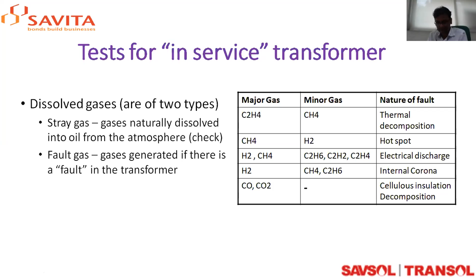So majorly, when you do the DGA, you have to keep an eye on methane, hydrogen and acetylene generation. In a transformer, acetylene and ethylene are the most critical; when there is an increase, the situation is alarming. You have to look into it and attend to why it is happening. You have to really resolve where these gases are generating from, where the hotspots are, and attend to those. Next slide.